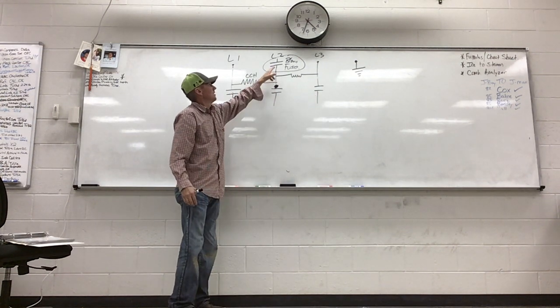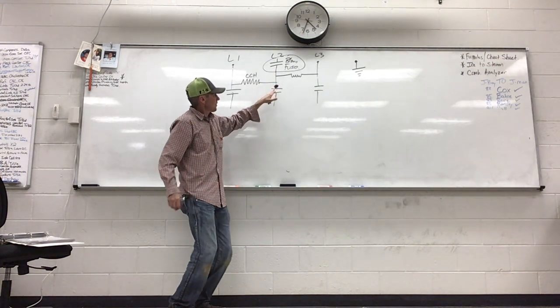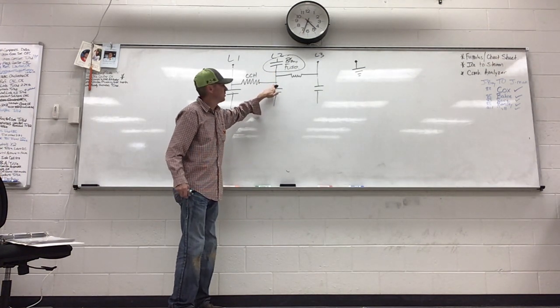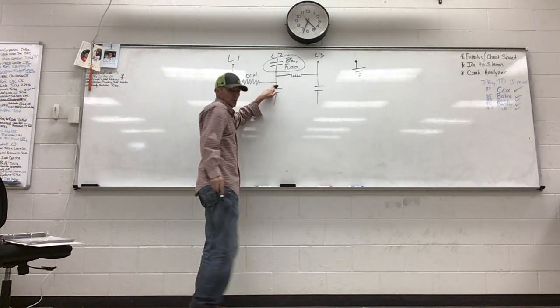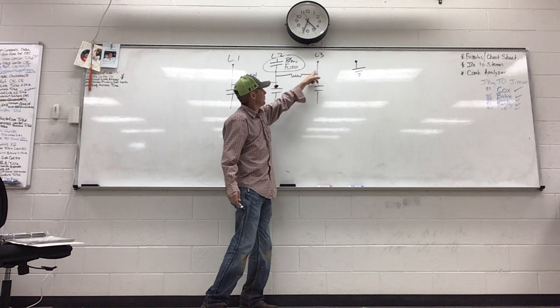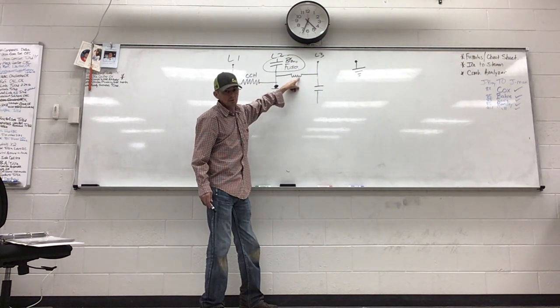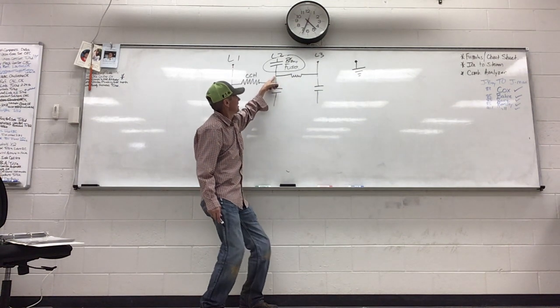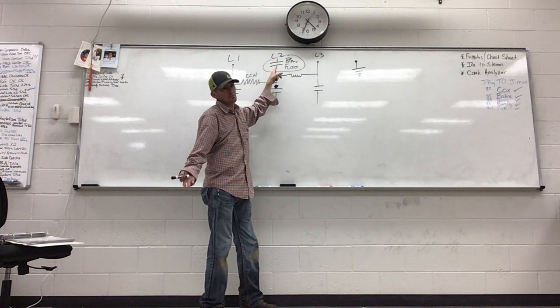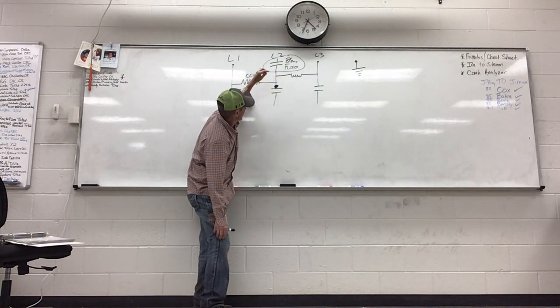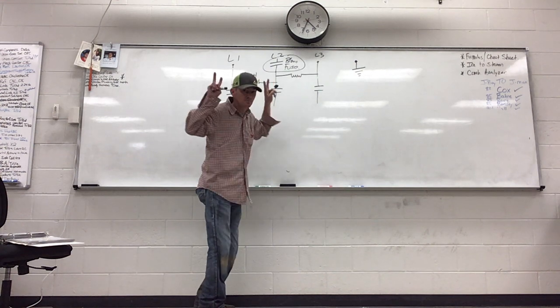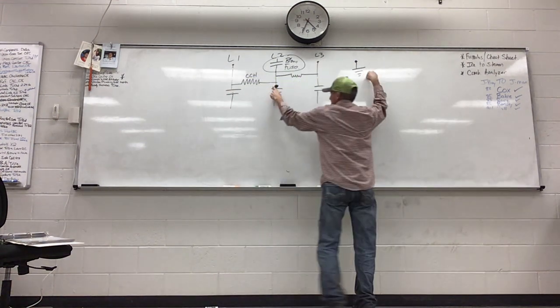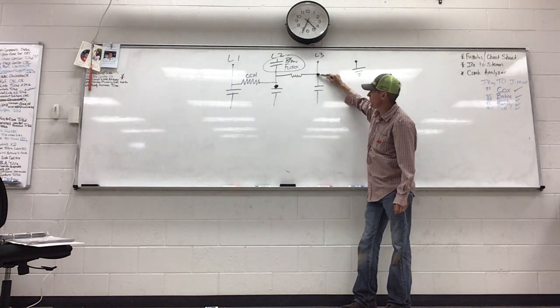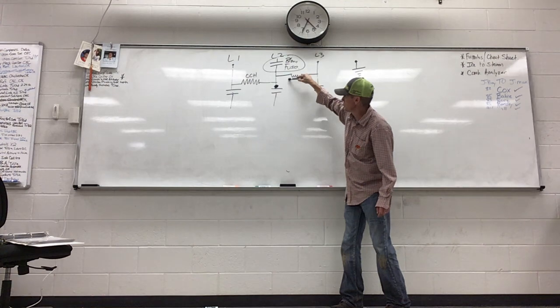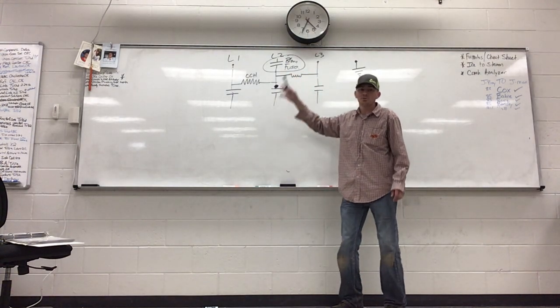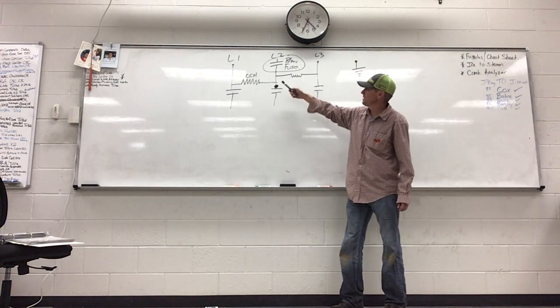And guys, the reason why, I already told you we got this blown fuse, but when you check L2 to ground and you see that 120, we're back feeding. Because look, we got L3 coming in, feeding the primary of the transformer, and it's sitting at L2. It's trying to get back on L2, but it can't because it's got a blown fuse. When we put our meter right here and check from L2 to ground, you see that 120? We're actually reading this L3 that's coming down, going through the primary of the transformer, and sitting here at L2 trying to find its potential difference, trying to get back to the other side of the line, right? And it can't because we got a blown fuse.